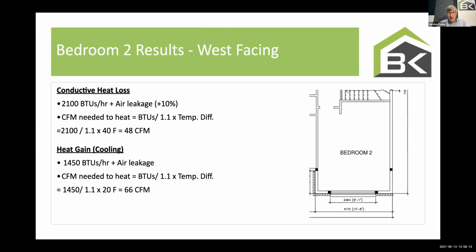I don't have to wait for the hottest or coldest day. I just need to know, am I getting 48 CFM out of that vent? Am I able to get 66 CFM out of that vent? That's what I need to know. And of course, you're going to say, well, I need 66 in the summer, and then I need to close it down in the winter. Yes, that's natural. That's normal. That's called being in Canada.